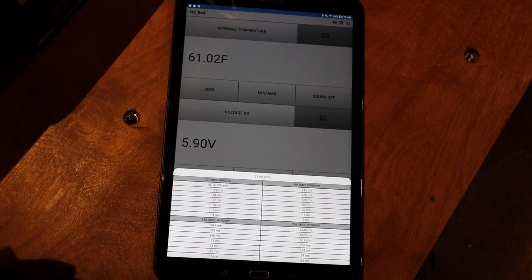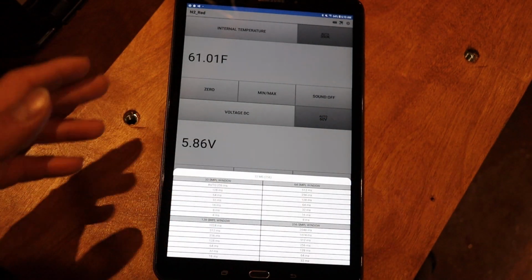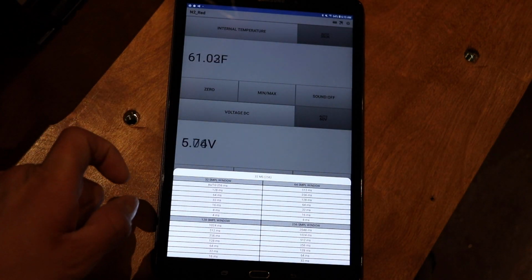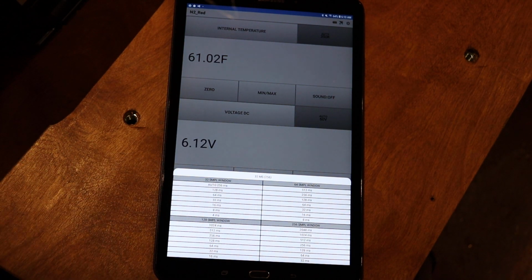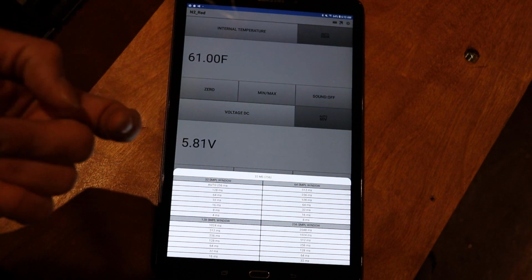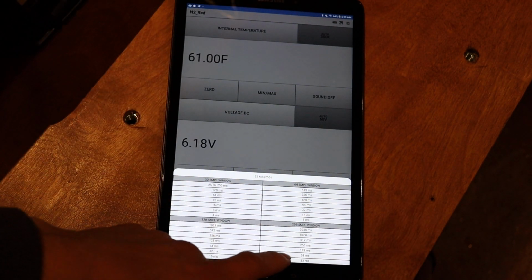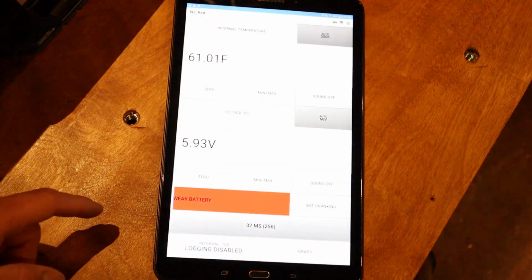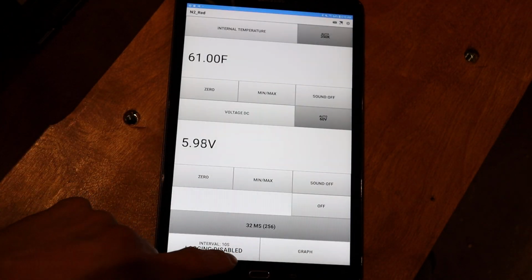And so in all technicality, we can take measurements at 4 millisecond data points, every 4 milliseconds, or bigger data points. However, if you want a very fast measurement and a very small window, it's still going to be 32 samples at 4 milliseconds apart. However, the window is going to be really small, so you're going to have to start stitching together these windows. So the larger window at 256 at 32 milliseconds is really the optimal way to get these measurements. And we'll see here in just a moment. I'm going to show you some stuff. Let's go ahead and turn this off. We are not using our tests.